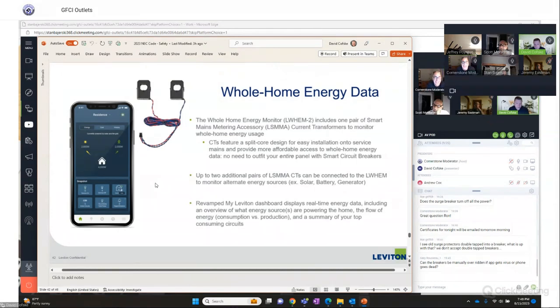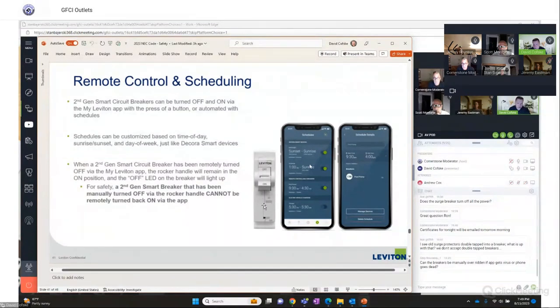From the app, you can invite people to have access to your house. That control is in there. But most of what we're seeing on the AFCI side of things is noise, and noise is causing a lot of nuisance tripping. Because we have technology built into our circuit breaker, we actually have a chip inside the breaker. We can update the firmware on the circuit breaker to ignore certain noises that were causing that breaker to trip. So Leviton, I think, is really the only manufacturer out there that can do that. I've done it at many properties throughout Connecticut. When we've run into those situations, I can actually get it fixed for you.